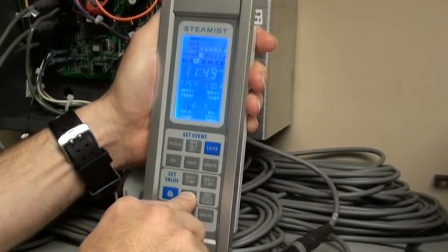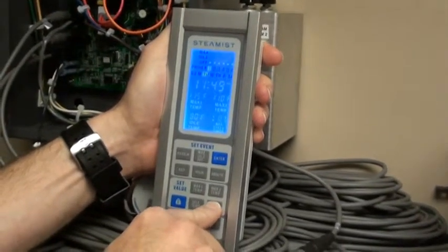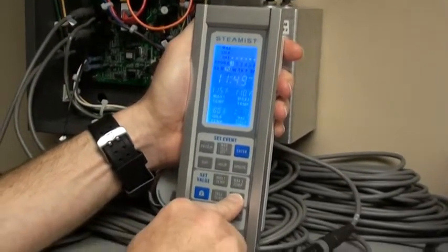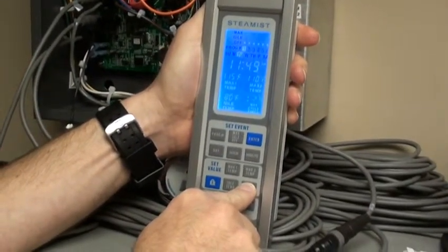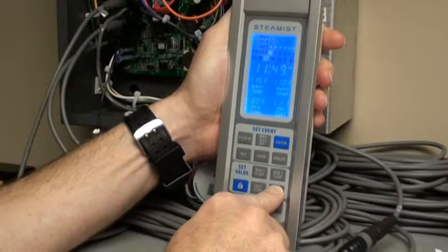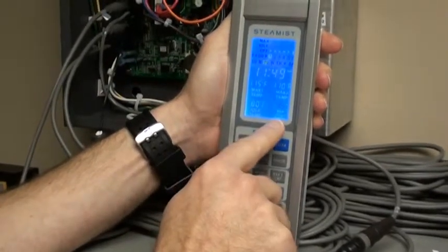Okay, idle temp, at which we want both rooms to be held, we'll set it to 80 as the minimum. Max cycle timer, we will set that to 30 minutes, which simply means that both rooms will hover at 80 degrees all day long, so the rooms are not ice cold, they're warm, the walls are warm, the machine is pressurized, ready to go. Anytime a user turns the system on for room 1 or room 2, the max temperature in max mode will be at 115 for, let's say, men's, or 110 for women's. It'll run there for 30 minutes. After 30 minutes it'll go back to the idle temperature.